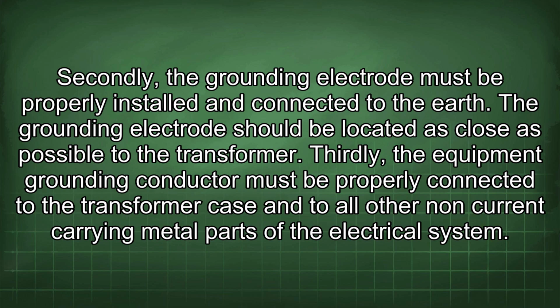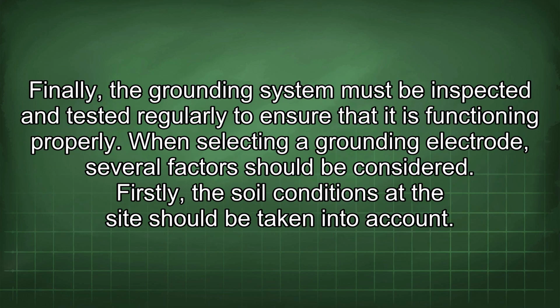Thirdly, the equipment grounding conductor must be properly connected to the transformer case and to all other non-current carrying metal parts of the electrical system. Finally, the grounding system must be inspected and tested regularly to ensure that it is functioning properly.